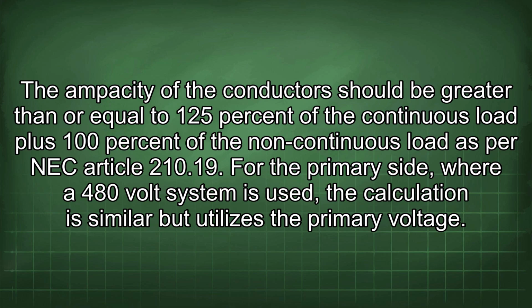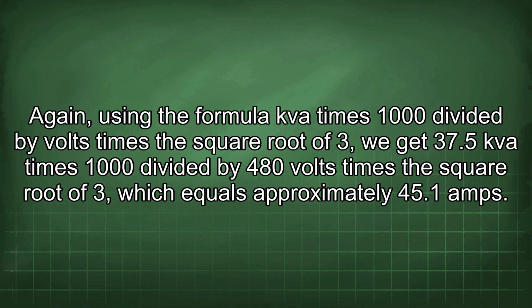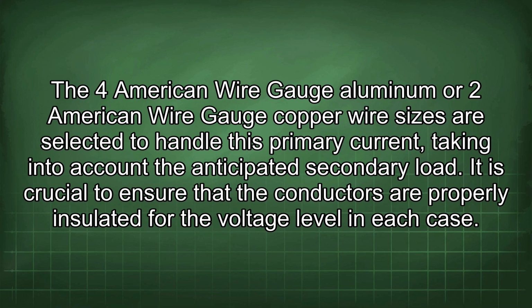For the primary side, where a 480-volt system is used, the calculation is similar but utilizes the primary voltage. Again, using the formula kVA times 1000 divided by volts times the square root of 3, we get 37.5 kVA times 1000 divided by 480 volts times the square root of 3, which equals approximately 45.1 amps. The 4 American wire gauge aluminum or 2 American wire gauge copper wire sizes are selected to handle this primary current, taking into account the anticipated secondary load.